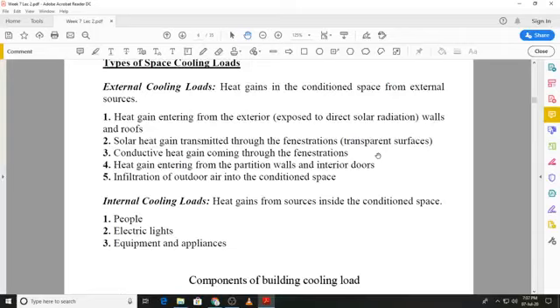The infiltration can occur, of course, because when doors are opened as people enter and leave the conditioned space, there will be some entry of the outside air into the conditioned space. In addition, the frames of the doors and windows also have small gaps through which this air will enter into the conditioned space.